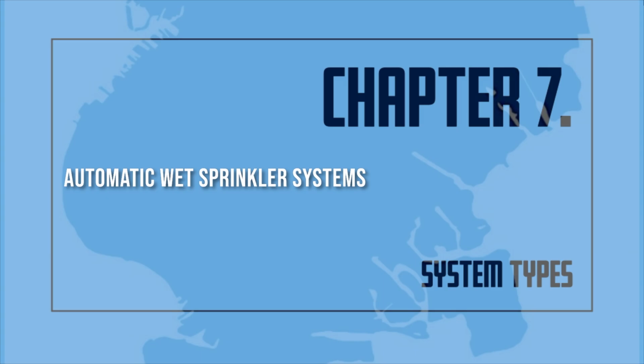Most standard sprinkler systems have devices that automatically sound an alarm when a sprinkler head discharges water. This alarm is usually an audible signal in the building. In many cases, they also give an alarm at a remote location, such as an approved central station company. The central station company monitors the entire fire protection system for water discharge and problems with the equipment. When water discharge or equipment problems are identified, the local firehouse is immediately notified. This allows the fire department to gain control of a fire as quickly as possible. Water is rarely discharged accidentally from sprinkler heads.